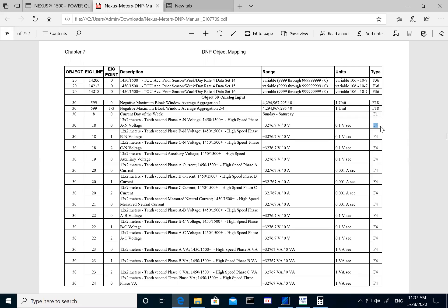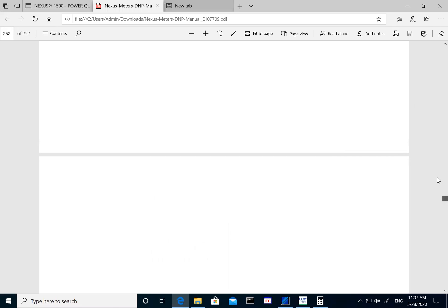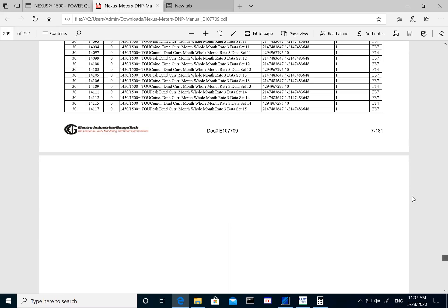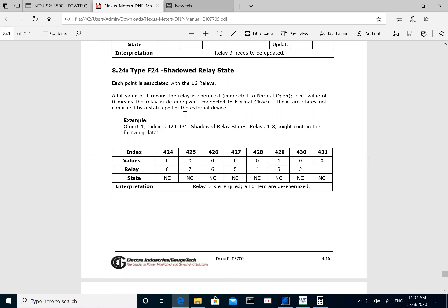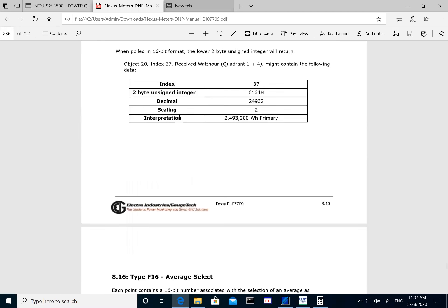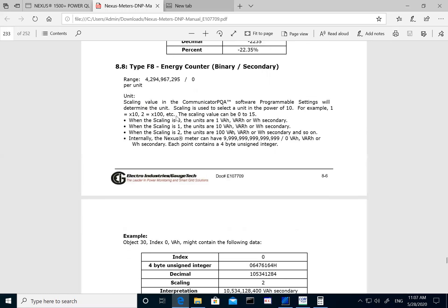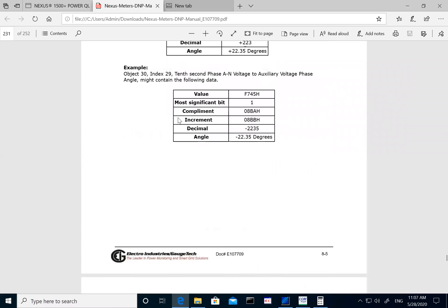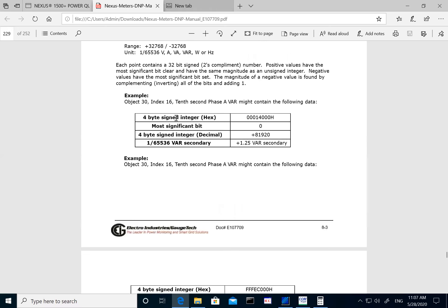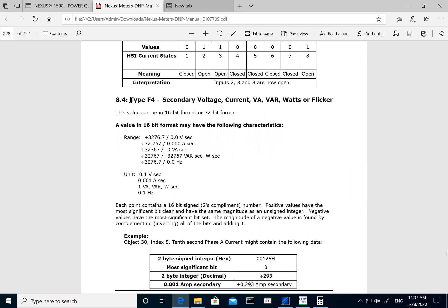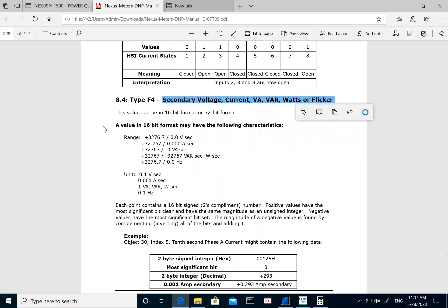That's why we list these types at the end. For example, this one is F4, and at the end of the manual we list all descriptions for the types. If I scroll down to F4 — this is the type F4 which is my secondary voltage, current, and power readings. It shows you the math and the typical range it could support — for example, voltage ranges from 0 to 3,276.7.